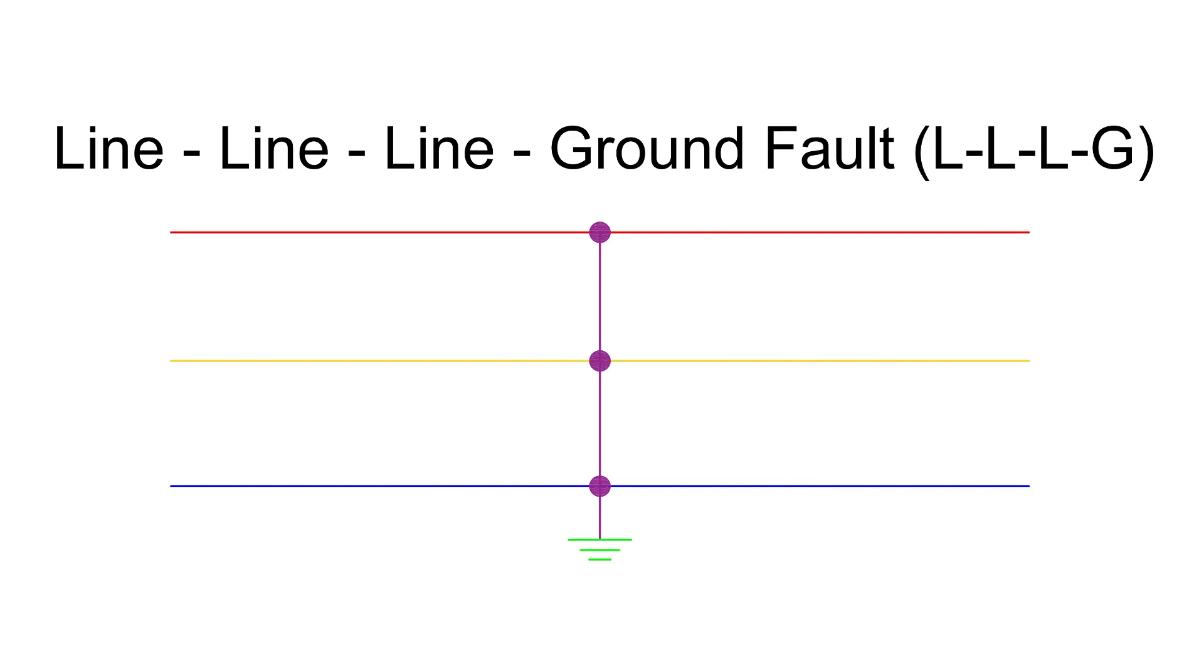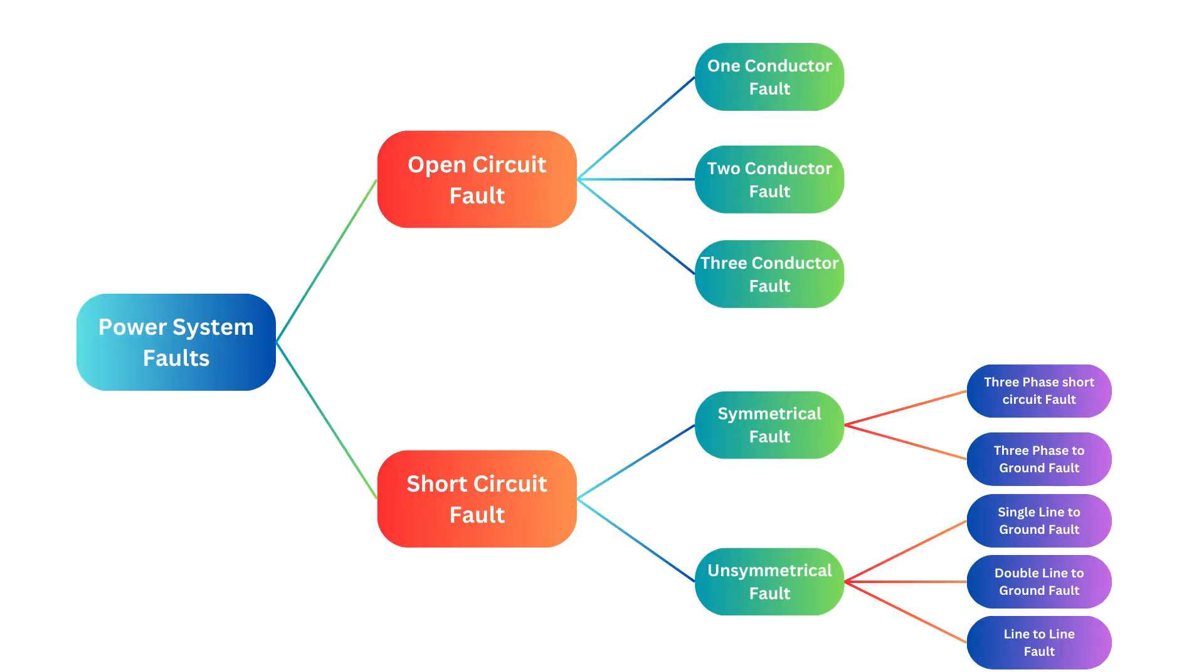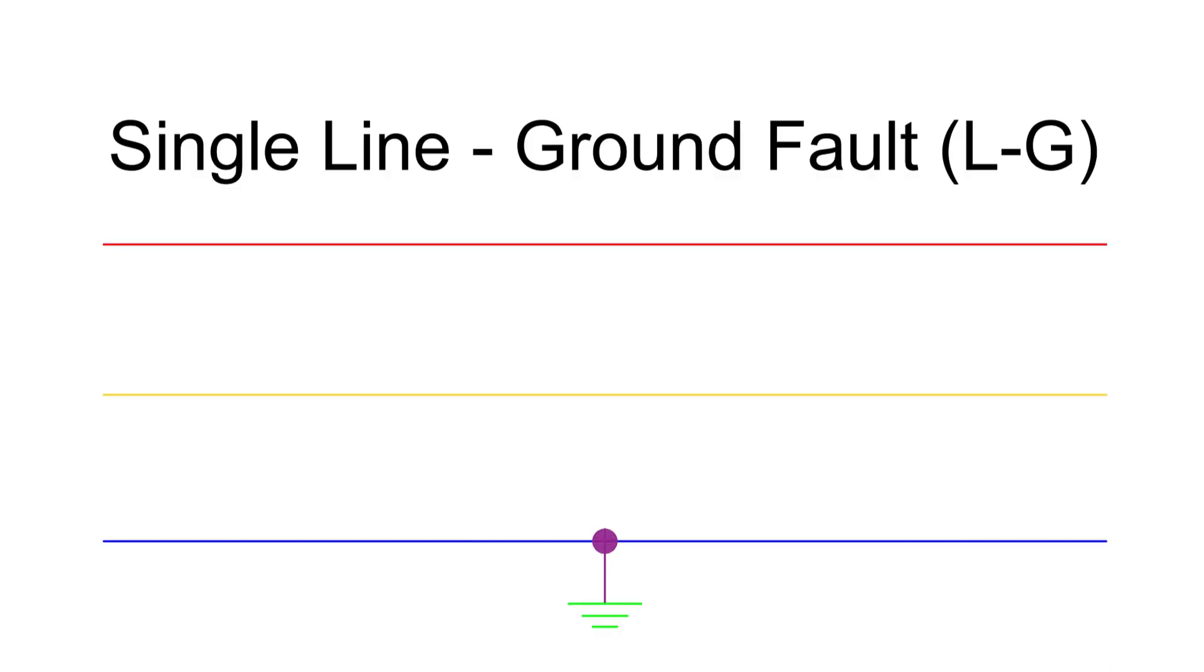Unlike symmetrical faults, unsymmetrical faults result in unbalanced current flow. These include single line-to-ground faults, the most common fault, occurring 70-80% of the time, happens when one conductor falls to the ground or contacts the neutral.